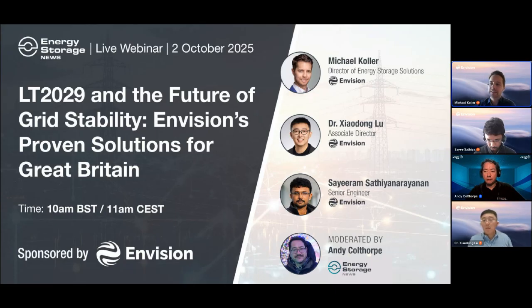The really interesting case is inertia, because inertia does potentially stress the cells to a certain degree, because you have high currents for a short period of time during the provision of inertia. And this is where the benefits of an integrated R&D roadmap come into play. At Envision, these specifications, or these short-term overloads, have influenced our battery cell development. And we can say, given the frequency and expectations for currents and the sizing of our system, there is no impact of these inertia events on the degradation curves and the SOH of a system operating in the UK market.